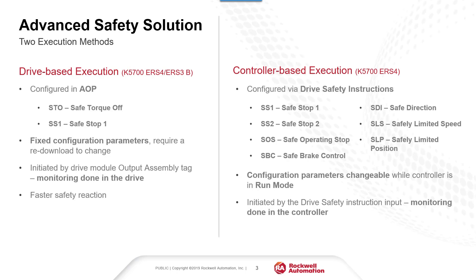Execution of a drive-based safety function is initiated via a drive output assembly tag. Once initiated, the monitoring of the safety function is done in the drive. Because monitoring is done in the drive, safety reaction time will be faster.